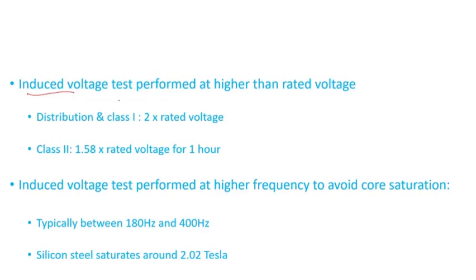Induced voltage test is a very common test performed on transformers and other equipment, but in this particular video I'm talking about transformers at higher than the rated voltage. By IEEE, for IEEE designs, if you have a distribution or Class I transformer, the voltage is two times the rated voltage.